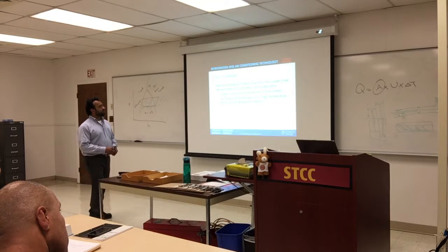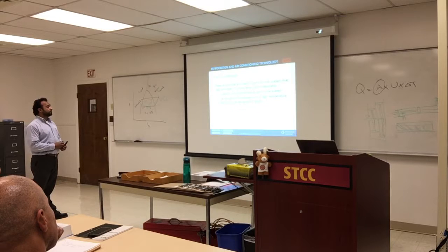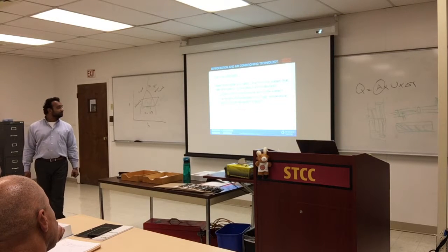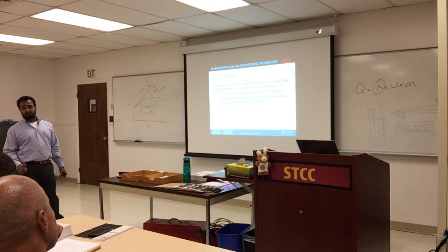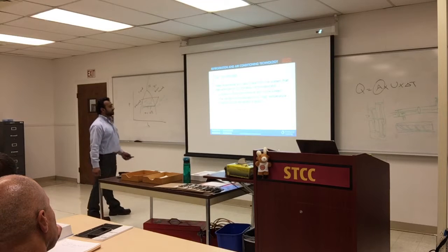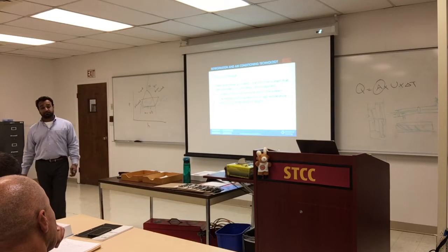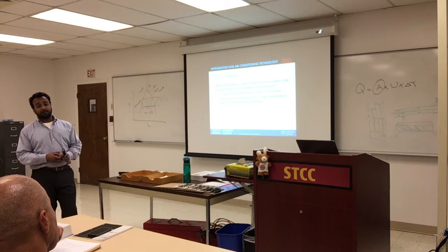So the condenser again rejects the heat, sensible heat and latent heat from the system that was absorbed by the compressor and the evaporator. You find it in the high pressure side of the system, so the high pressure also has the high temperature. The refrigerant condenses from high temperature vapor to high temperature liquid.